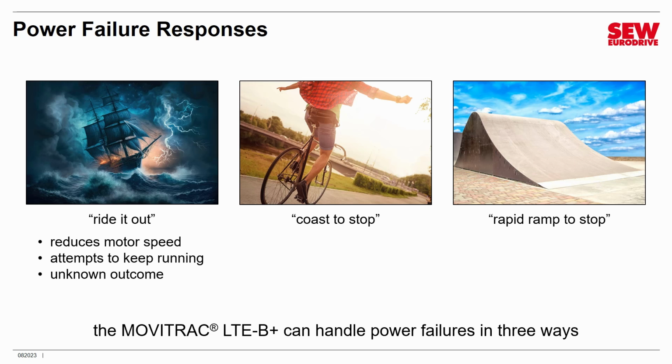So what will happen in a ride it out situation is the VFD will reduce the motor's speed, but it will attempt to keep running using the energy in the capacitors. Now, if the power comes back quickly enough, then this will work. It'll come back up to speed and all will be well. But the outcome is ultimately unknown. It really just depends how long the power is down. If the power is down too long, eventually the capacitors will run out of energy and the motor is just going to go into coast mode. So this is okay if you expect that power will come back, that it'll just be a short blip, but if it's too long, you could get in trouble.